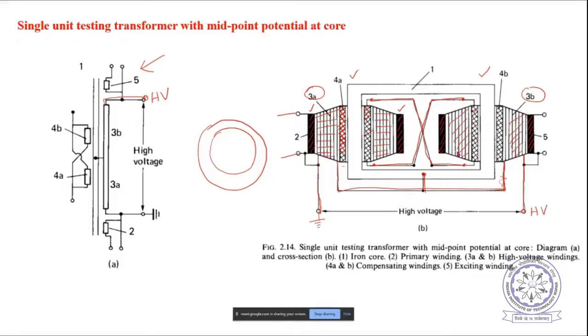Voltage stress in the middle means? What is the middle? In that core, there should not be any voltage stress, because if you directly connect the windings without phase opposition, then the dot polarity will be near each other, like in the same phase. That would mean there is a voltage stress, because plus would be near plus, and minus would be near minus, so the voltages would oppose each other. But if you keep it in phase opposition, then the dot polarity will be different, 180 degrees apart.